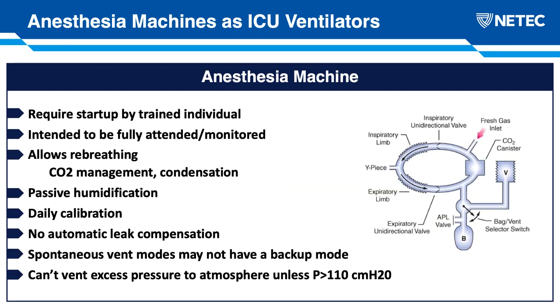So the differences in the way that we think about an anesthesia machine from an ICU ventilator, there are many, but here are the basic considerations we need to work through as we think about deploying an anesthesia machine as a fixed ICU ventilator. Number one is that much like an ICU ventilator, these machines need to be started up by a trained individual. And the difference here, of course, is that the trained individuals for most anesthesia machines are anesthesiologists and anesthetists. Also, these machines are meant to be used in anesthetizing locations and are therefore designed to be fully and continuously attended by trained personnel and monitored all of the time. A couple of the implications of that are that our alarms aren't as loud. The max volume on most anesthesia machine alarms is not as loud as ICU ventilators.